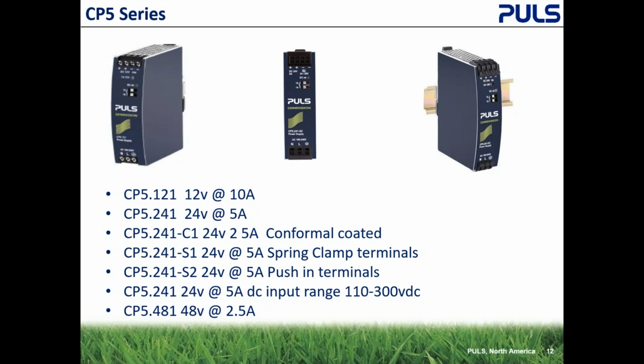So why would you need a DC input? People running redundancy sometimes want to run one power supply off an AC, another power supply off DC. So you can put 10, 12 volt batteries in series, got 120 some volts, 128, 130 volts, run that into another power supply and take both outputs in the redundancy module. So if you lose a main AC and it's a very critical application, you still can run your load.